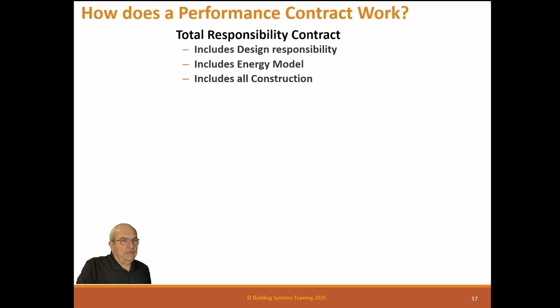So a total responsibility contract includes design responsibility, modeling, all construction, commissioning, and a performance tracking system. It may also include an analytic data software package—may not, because they're expensive, but if included, it helps. It includes one year of optimization for operation and performance verification. Performance is proven at the end of the performance tracking and verification period.